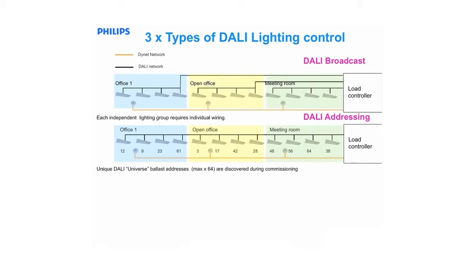The advantages are that it's easier and cheaper to install. Any future changes to the required lighting groups are possible simply by reassigning the logical ballast addresses. No physical change to the lighting wiring is required.